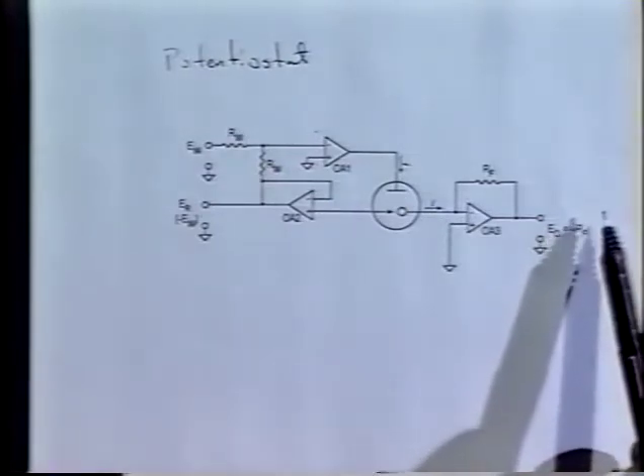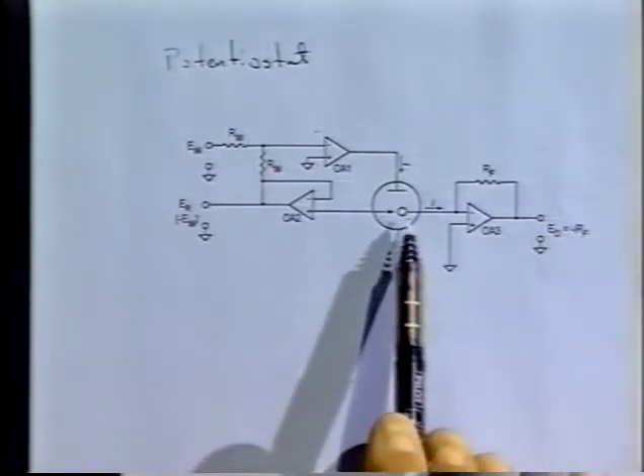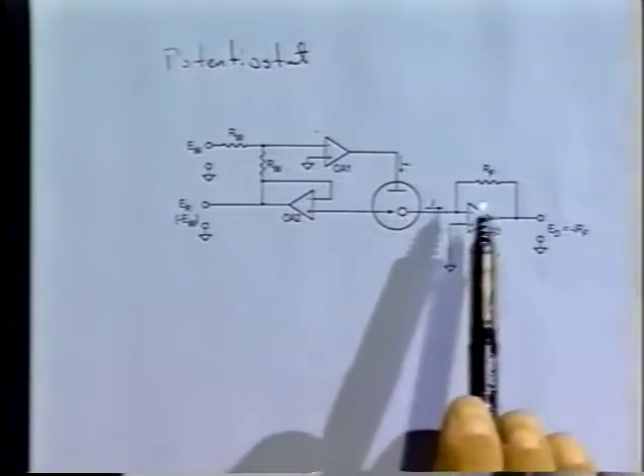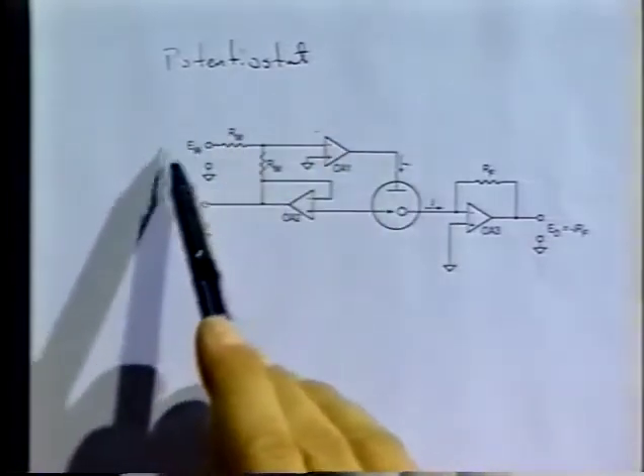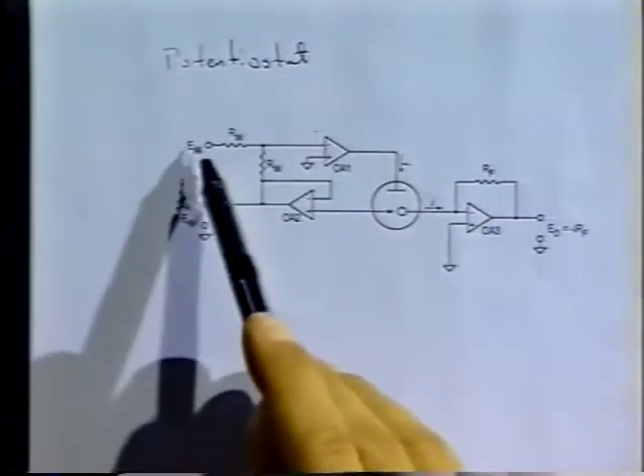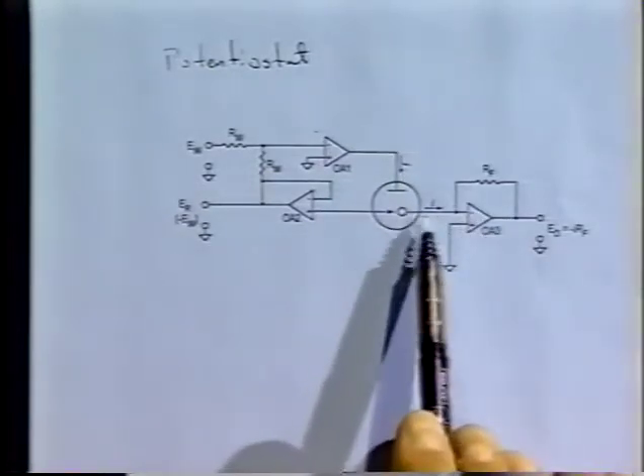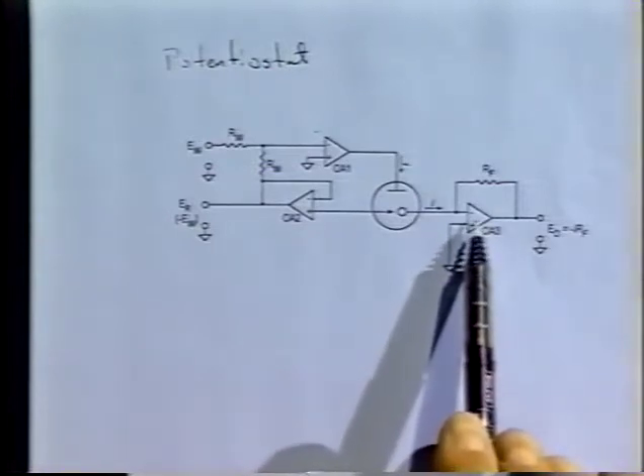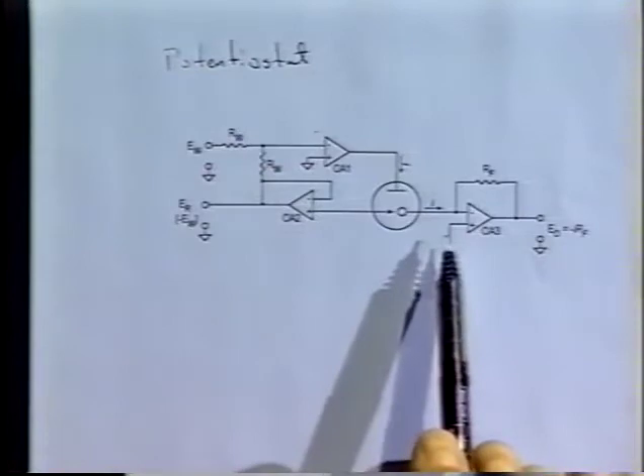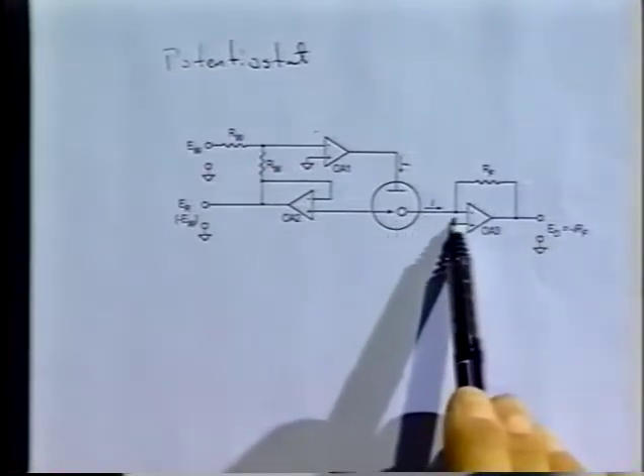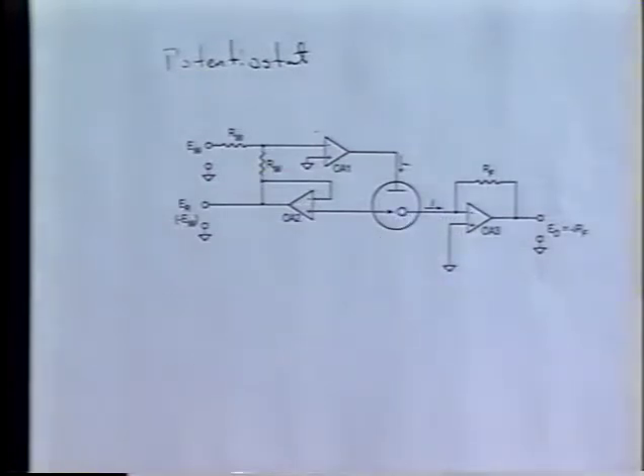This part of the circuit converts the working electrode current to voltage. In fact the potentiostat would work correctly even if the working electrode was connected directly to ground. The potentiostat part of the circuit is over here. Here we see the current flowing into this amplifier — that's a current follower amplifier. That point right there is virtual ground, so the working electrode is effectively held at ground potential throughout the entire operation of the instrument.